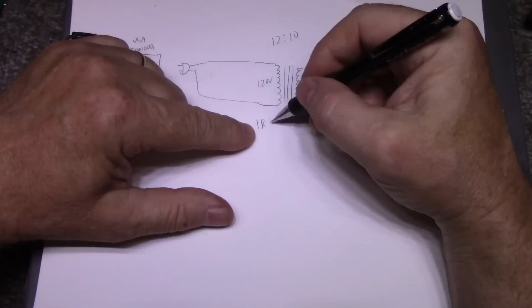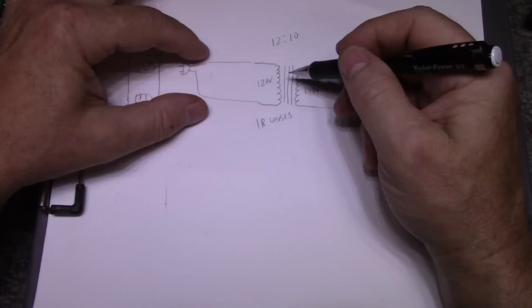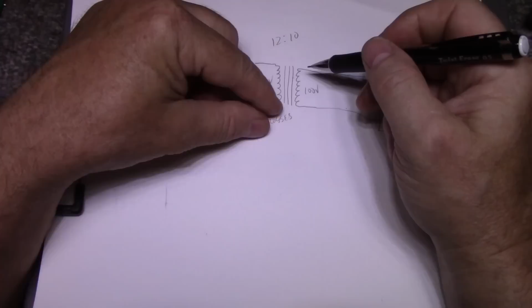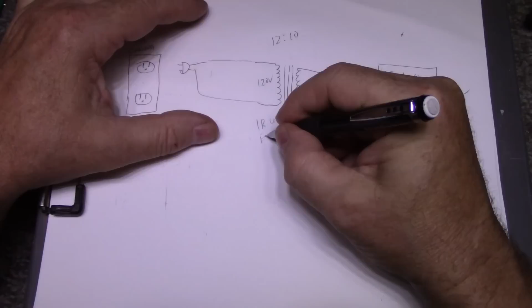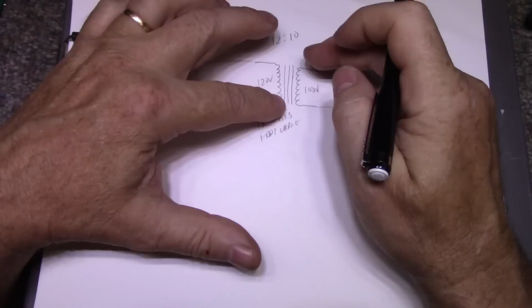IR losses is the resistance of this winding and the resistance of this winding, and the current flowing through it. And you're going to have hysteresis losses, the losses when the magnetic field changes 60 times a second in the magnetic core. You're also going to have eddy current losses, within the steel core itself, within the laminations.